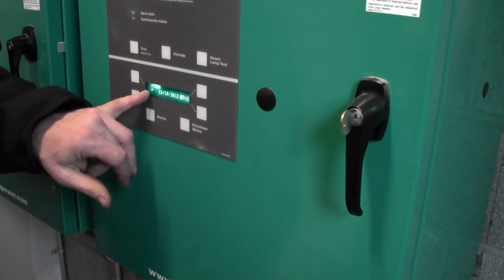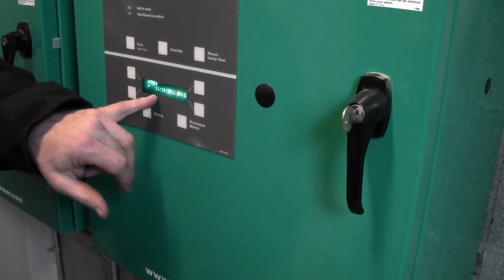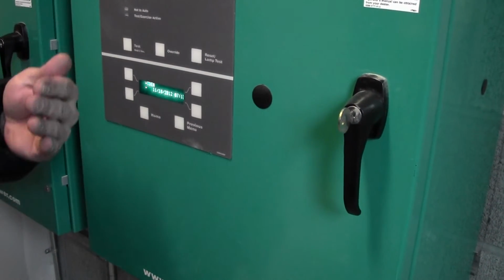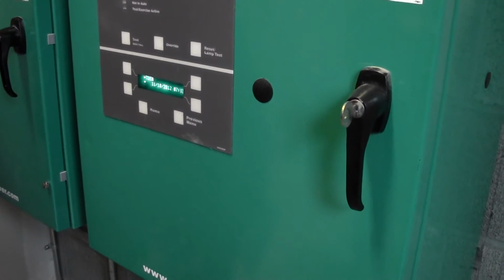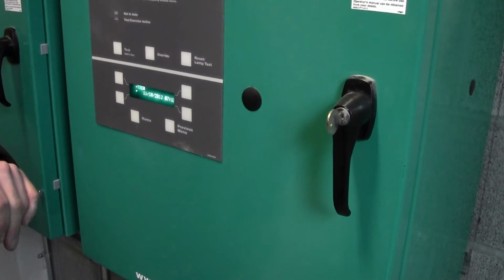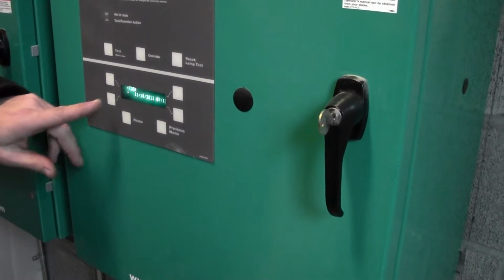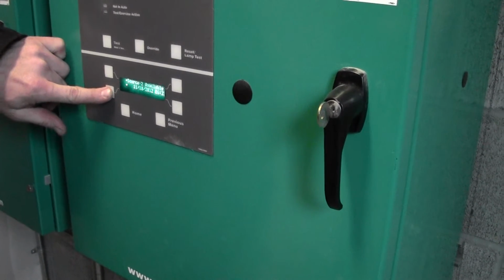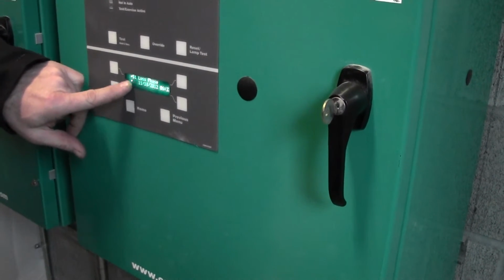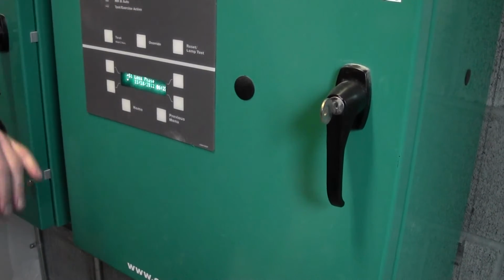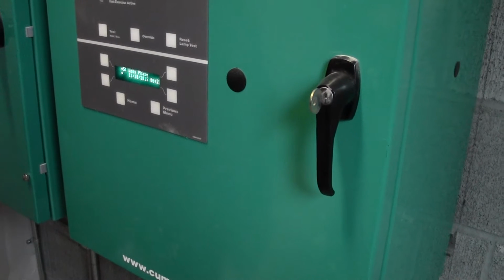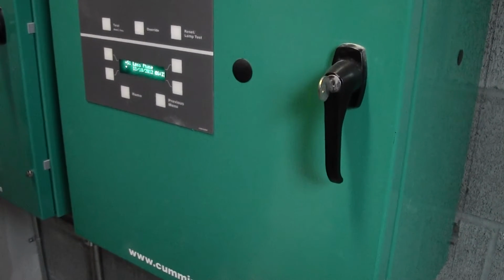Right. So what this is, at this time it started a timer for the emergency to go back to utility. And this is a 10-minute delay. So there are time delays that count down, but it breaks it all down for each event that's happened. There's a loss of phase, so it lost utility at some point. So it knew that, it says, hey, I lost it, it logs it. You don't need to log this kind of stuff though for the test.